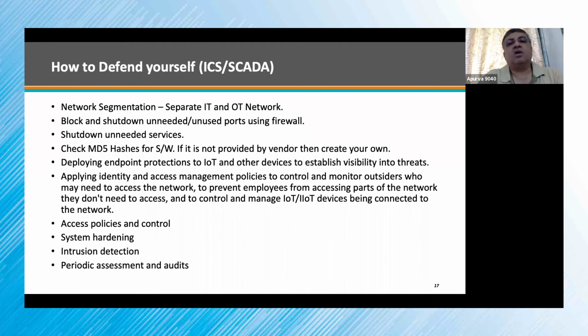Block and shut down all the unneeded, unused ports on your firewall. There are multiple ways you can connect your SCADA, because I have seen people, when they connect IT and OT, they do not put any firewall in between. They just put one switch and connect IT and OT. That is not the right approach. I would suggest you use a firewall.